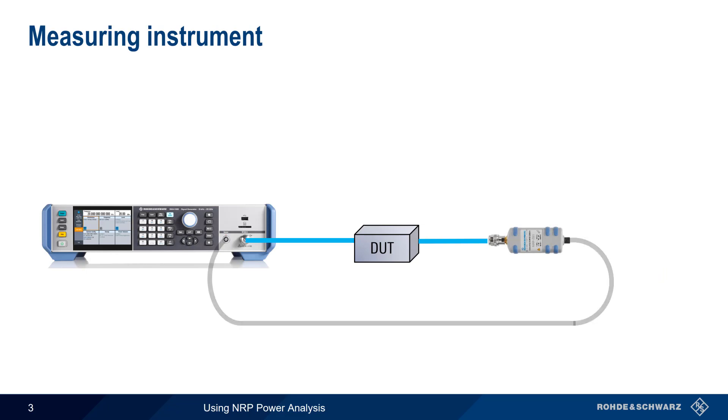In this case, the power sensor is directly connected to our signal generator. Our signal generator both controls and retrieves measurements from the sensor. Although this test setup is limited to scalar measurements, it can be used for a wide variety of applications.